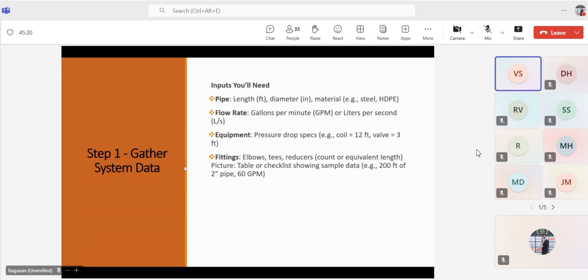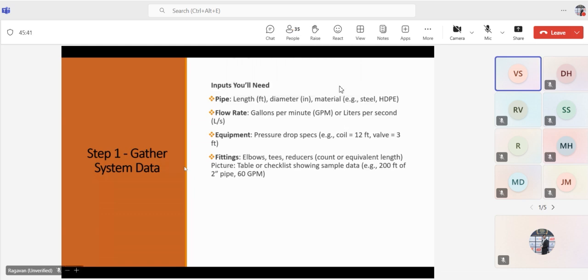Before proceeding with the hydraulic calculation process, you have to understand all these parameters in the pipe: what kind of pipe and material, and then the equipment losses and friction loss, and then the fittings losses. And finally, you have to consider a safety margin factor of 10 to 15% for the safer side. Here is one calculation example. Can you move on to the next slide? I will explain step by step.